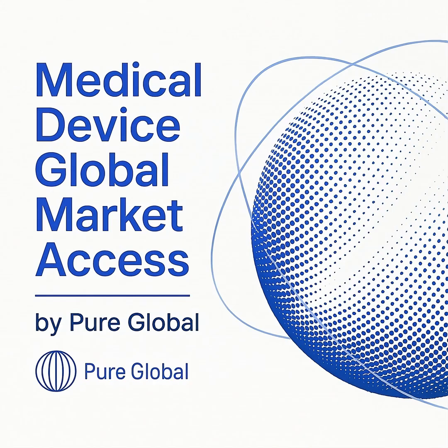At the forefront of global standards is ISO 13485. The primary international standard for medical device quality management systems. This standard lays down the requirements for a quality management system tailored specifically to the medical device industry, placing strong emphasis on risk management, regulatory compliance, and continual improvement. Alongside ISO 13485, other vital ISO standards include ISO 14971 for risk management, ISO 10993 for biological evaluation, ISO 15223 for labeling requirements and symbols, and ISO 14155 for clinical investigation standards.